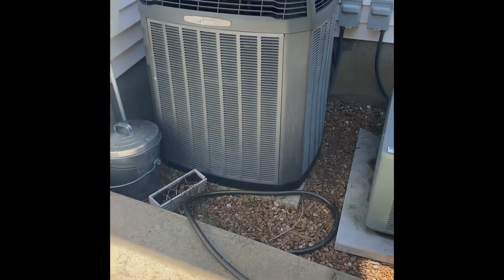There's a lot of algae and buildup in the drain lines. It looks like they run to a floor drain right here, so we'll go ahead and rebuild all of that just because of the algae buildup.